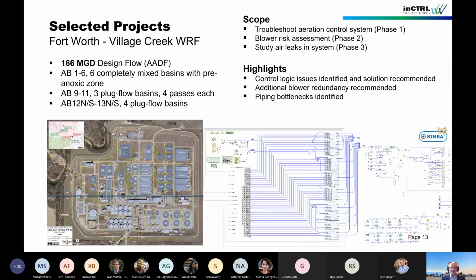In phase 1, we identified some control logic issues and recommended a solution to address them. We looked at the performance of the system and determined how the controller was performing, and came up with a strategy to improve that. We also found some airflow bounds imposed in the SCADA system that were limiting air to certain parts of the plant.